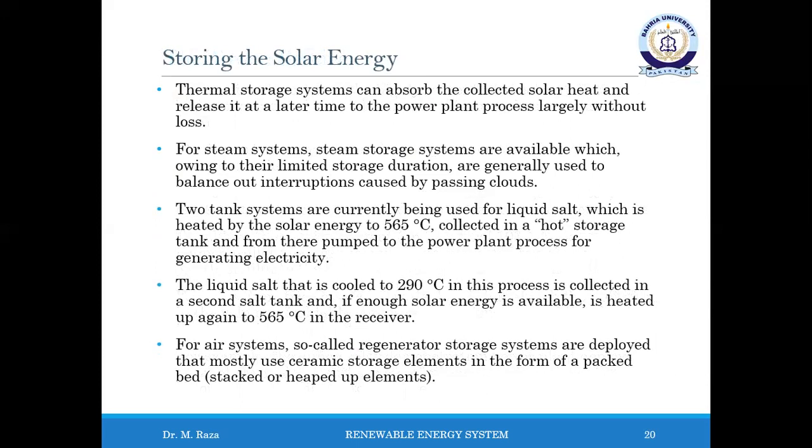Thermal storage systems can absorb the collected solar heat and release it at a later time to the power plant process largely without losses. The type of storage system depends on the heat transfer medium used. For steam systems, steam storage systems are available, which owing to their limited storage duration are generally used to balance out interruptions caused by passing clouds. Storage systems for steam systems with longer storage duration are still undergoing development, whereby a combination of sensible and latent storage is favored.